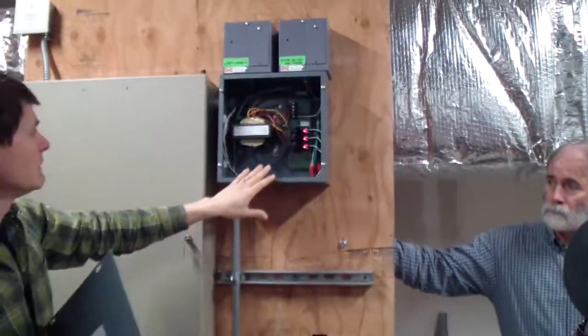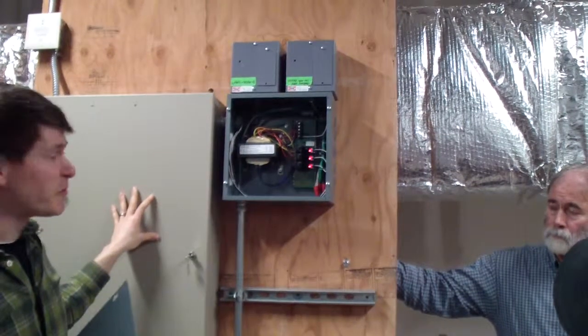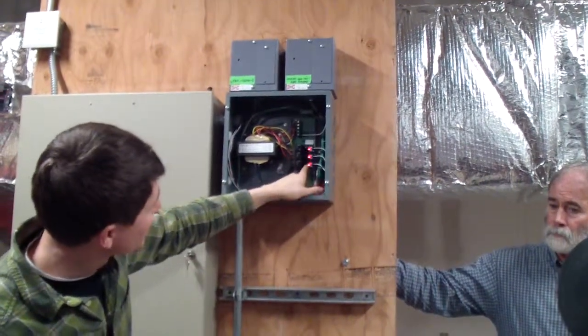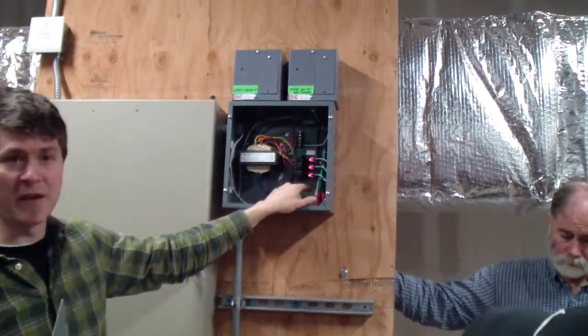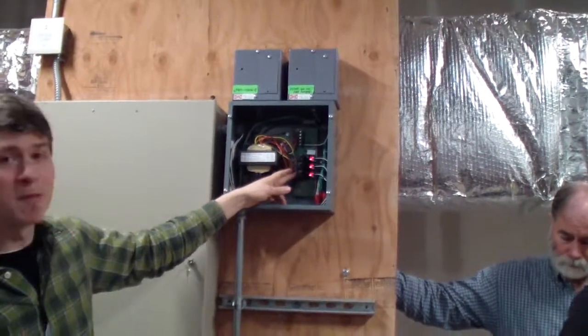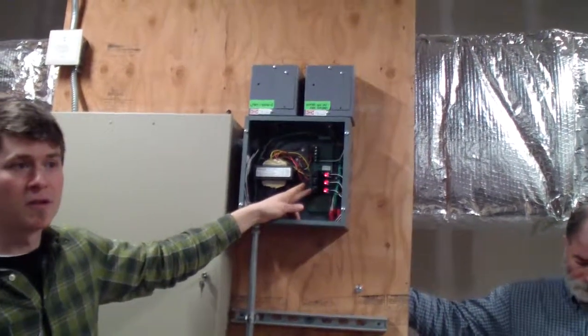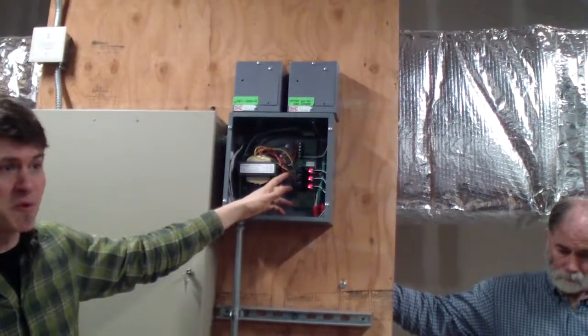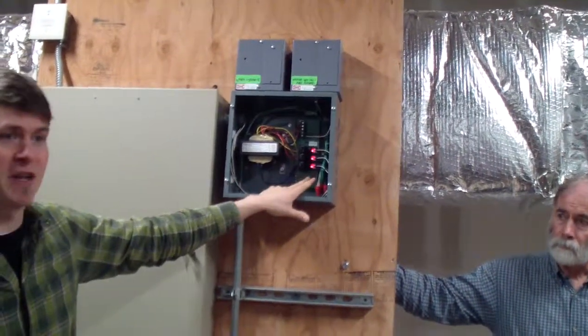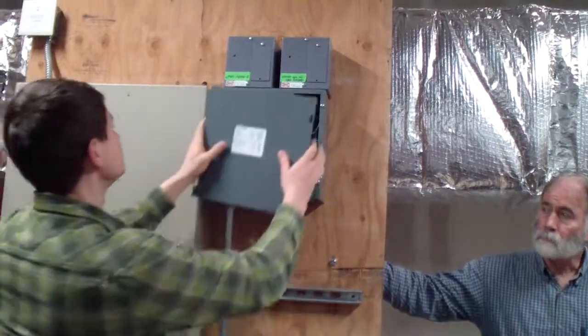This is the transformer that feeds our panel. So the same thing, you've got your on-off switches for your outputs coming out, and then you've got your resettable switches, overloads right here. So in case you do have some sort of fault, you do your first check here to make sure you got lights and to see what's going on.